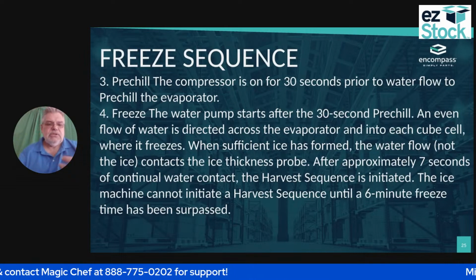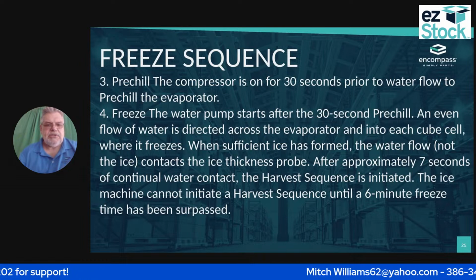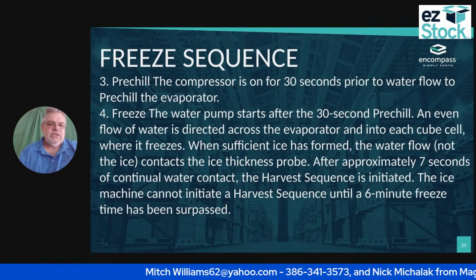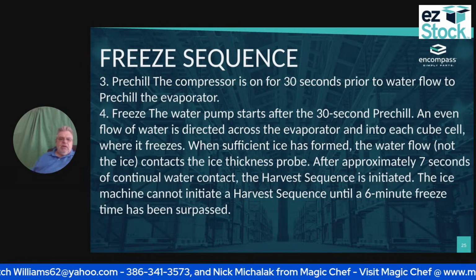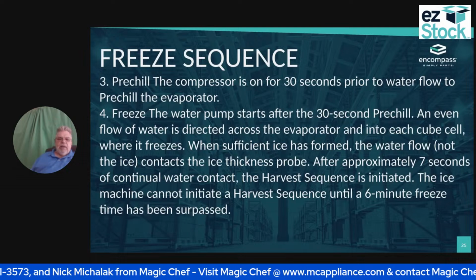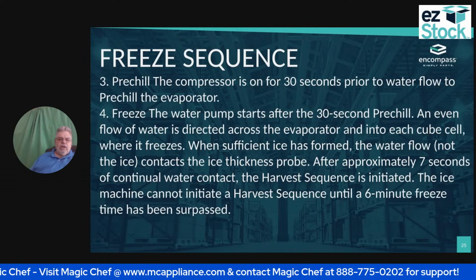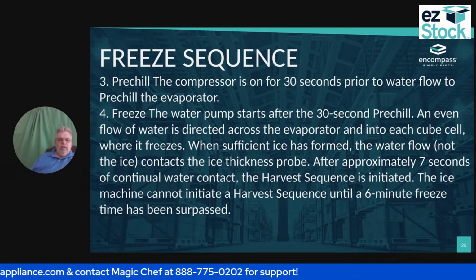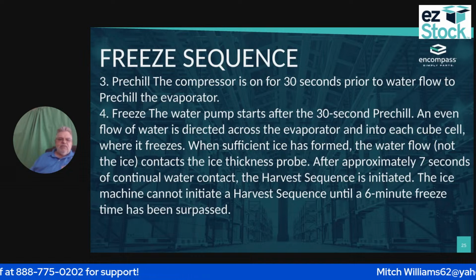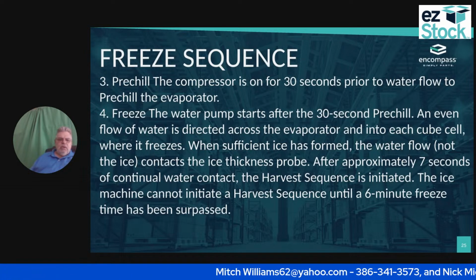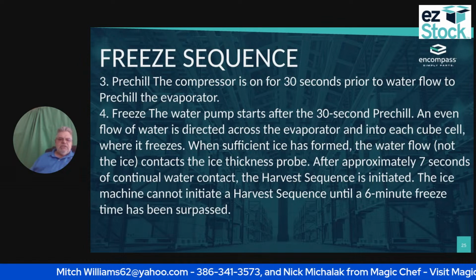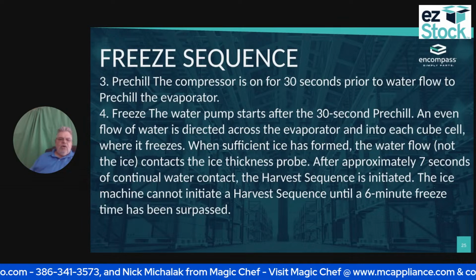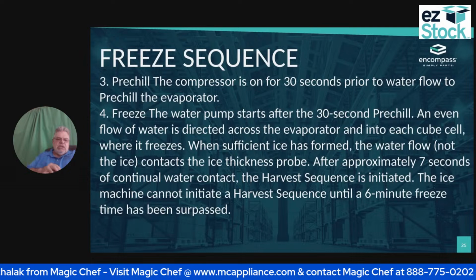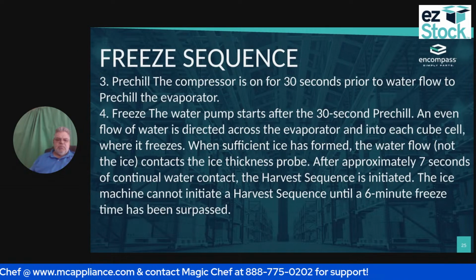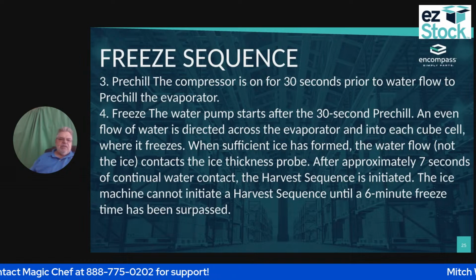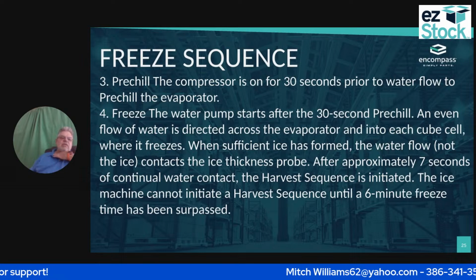Okay, the freeze sequence. So what happens is the pre-chill: the compressor is on for 30 seconds prior to the water flow so that I can pre-chill that evaporator. Then during the freeze, the water pump starts after my 30-second pre-chill, and the flow of water is directed through the evaporator and into the ice cube cell, where it freezes. When sufficient ice forms, the water flow contacts the thickness probe. After approximately 7 seconds of continuous water contact, the harvest sequence is initiated. The ice machine cannot initiate a harvest sequence until a 6-minute freeze has been surpassed. So it has got to be at least 6 minutes for the harvest cycle to start.